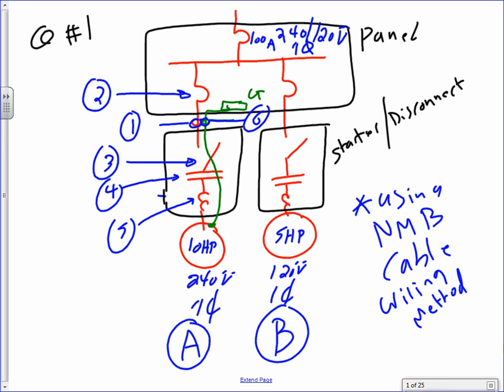I am using NM cable wiring methods. Very, very important. I'm using what type of wiring methods? NM. So I can't go to the 75-degree column. I have to go to 60 because NM is rated for 60. So that's basically the example that I have. I'm going to size these 6 things for these 2 motors. Any comments, any questions? Do you guys have enough? I'm going to give you a few seconds to sketch them, and then we'll go over the calculation. And this is a continuation of what we did yesterday.